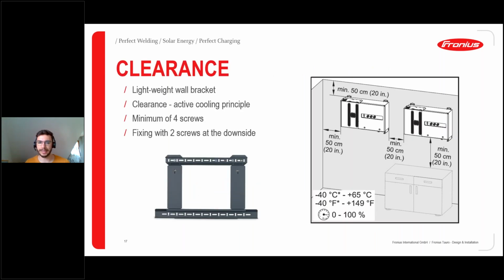Please make sure to keep clearance if you install multiple inverters next to each other, or if there are other objects nearby. Because we have the actively cooled system, we expel hot air from the sides and top of the inverter, so we need some clearance for this hot air distribution. Just keep in mind 50 centimeters on all sides, and then we're perfectly fine for other inverters or components installed next to it.